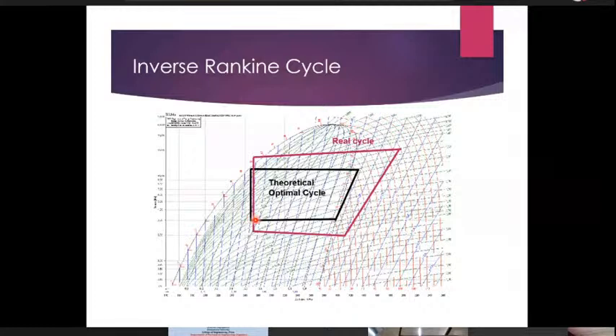In an ideal theoretical cycle, we will recover some work here. In a real cycle, we choose not to recover that work, and we use a simple device for isenthalpic or adiabatic expansion. Also, in a real cycle, because we want to make sure there are no refrigerant droplets, that means there is no liquid refrigerant, we like to have a certain element of superheat. So the move from the saturation curve to the point where we stop over here is the superheat region, and then we will have compression.